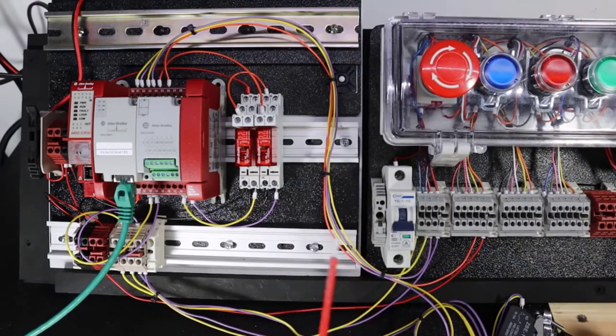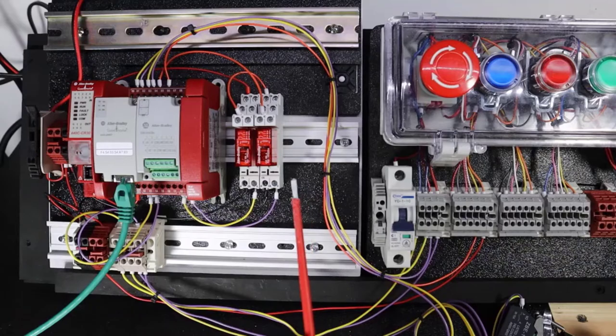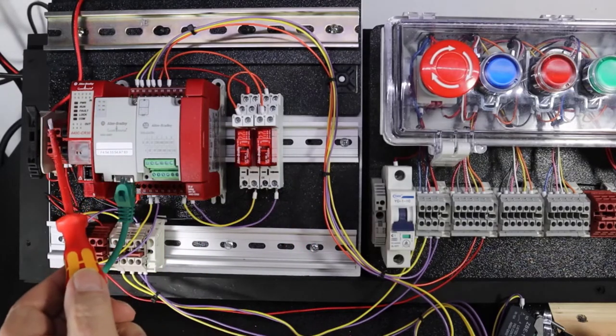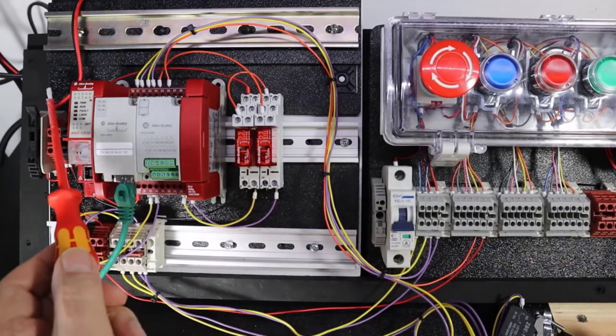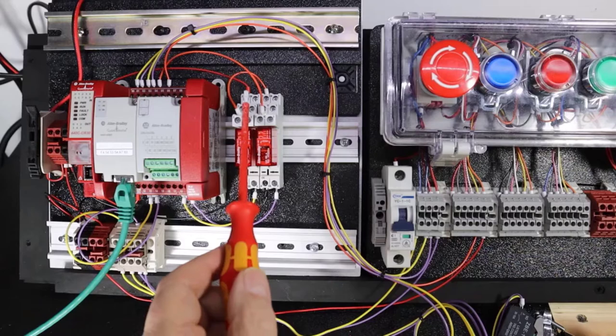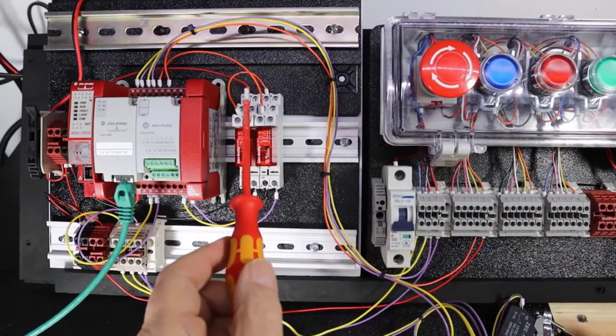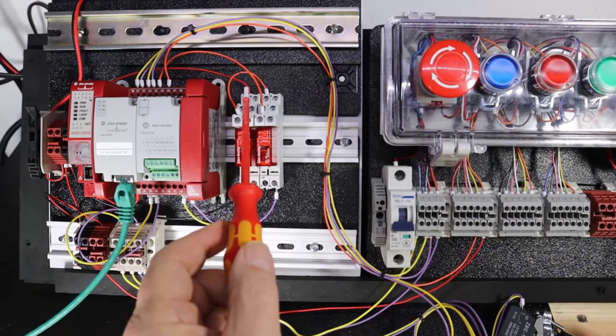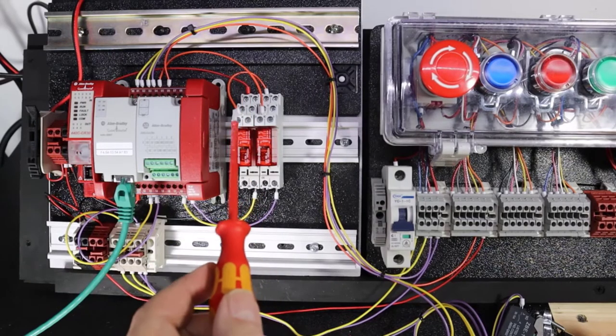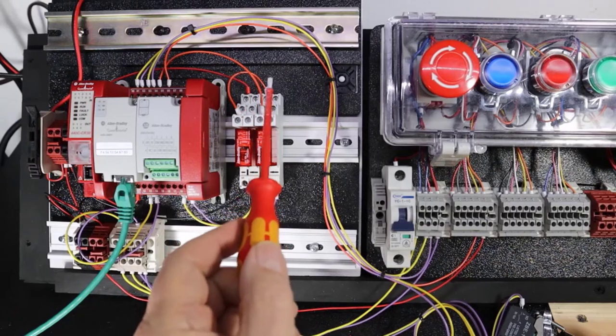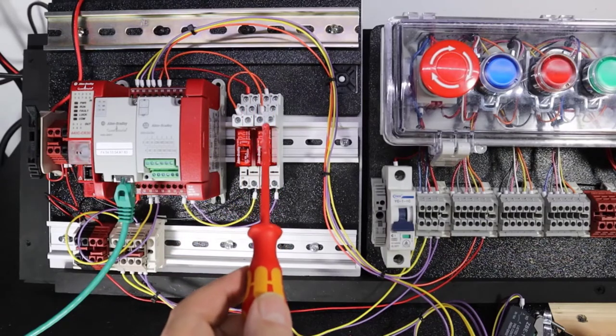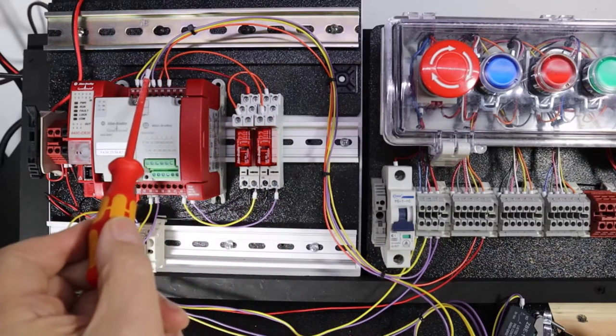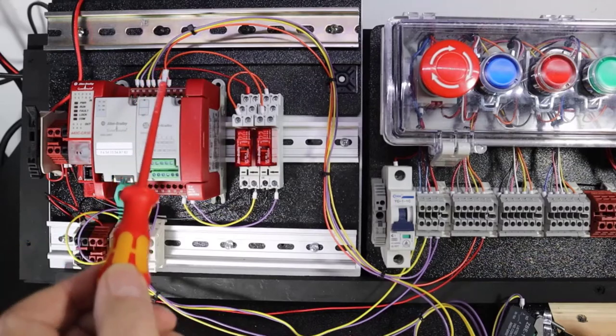For our feedback, we're coming right off of 24 volts DC through that red wire over to the common contact for this relay, out the normally closed, in the common, out the normally closed, and then we're going into input number 4.